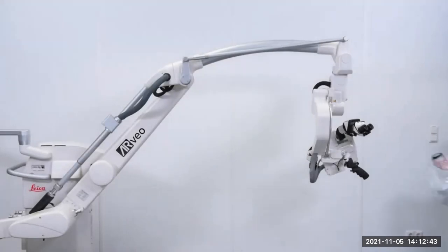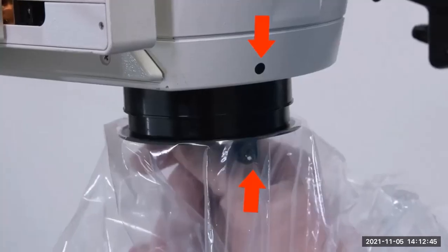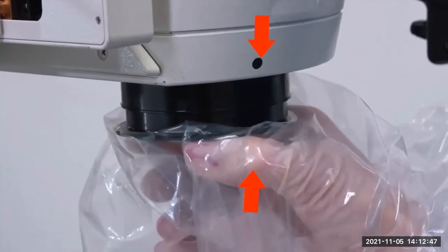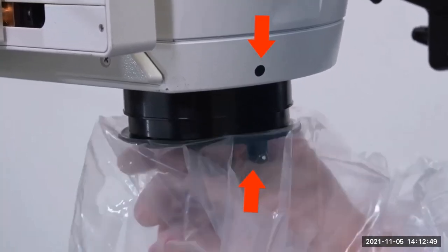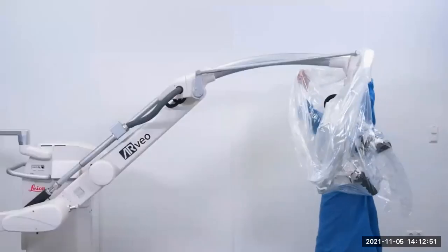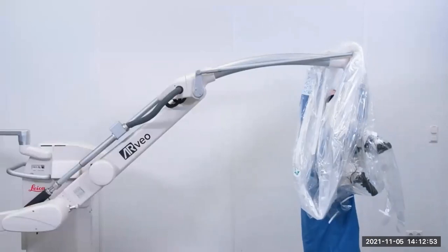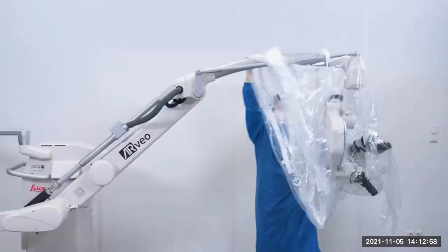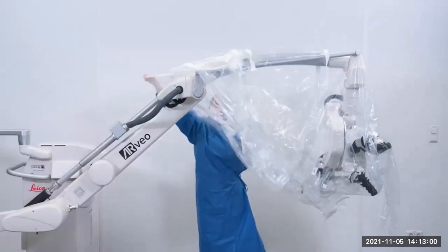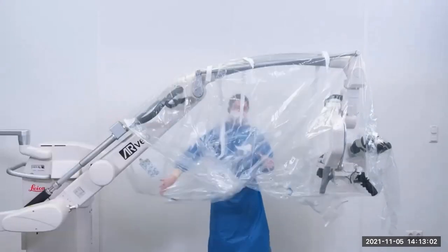Match the white dot on the lens cover with the black dot on the microscope, and twist to the right until you feel it is secure and locked into place. Move the drape over the microscope head and pull it over the rest of the arm. Your circulator can assist you, pulling the drape from inside over the microscope arm and wrapping the last band.